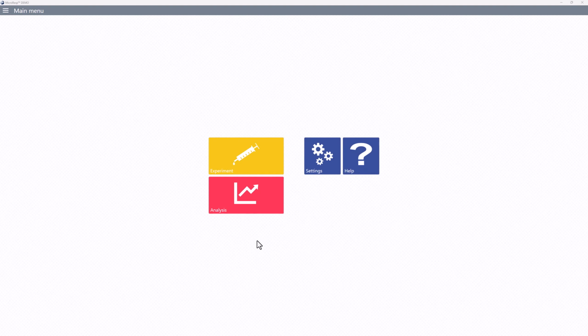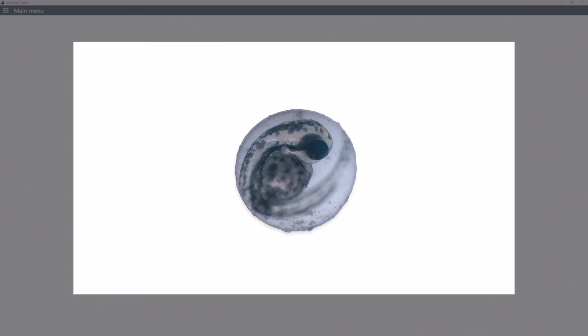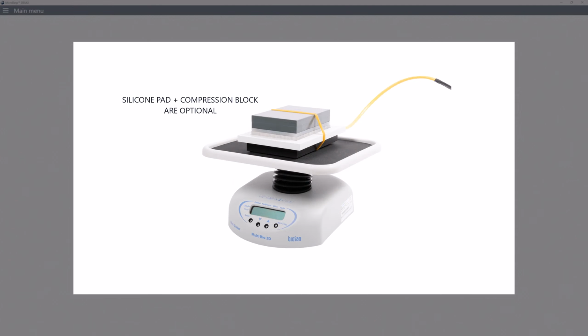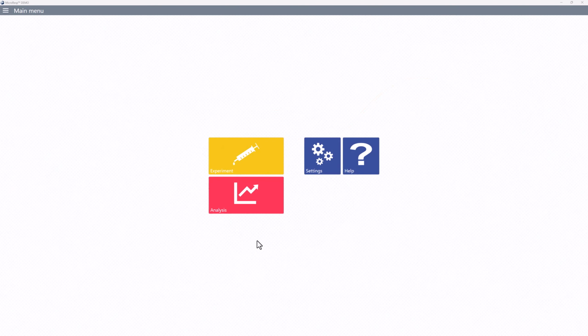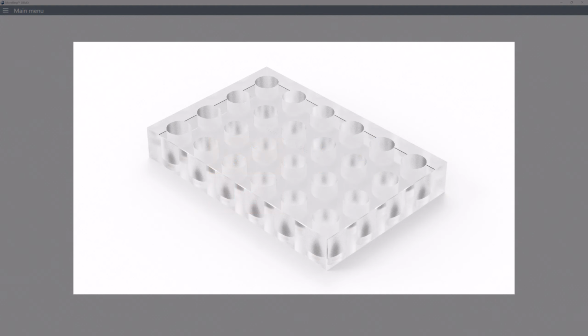For aquatic measurements on immobile organisms like eggs or embryos, we recommend placing the reader and the plate on an orbital shaker table to somewhat agitate the water, as this will reduce oxygen stratification inside the wells. Cleaning the glass plate can be done using ethanol, bleach, or mild detergent, and then rinse with demi-water. Now allow the plate to dry.